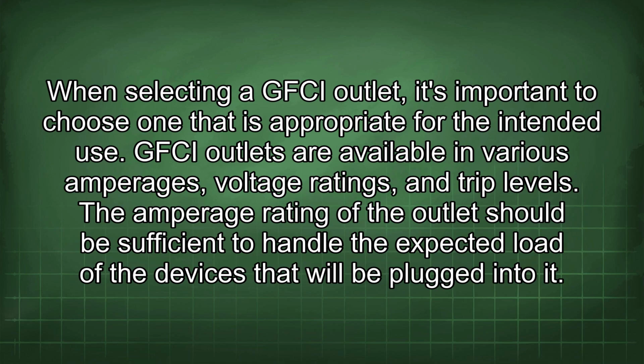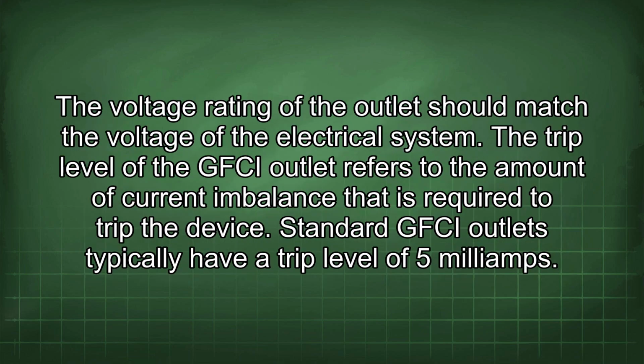When selecting a GFCI outlet, it's important to choose one that is appropriate for the intended use. GFCI outlets are available in various amperages, voltage ratings, and trip levels. The amperage rating of the outlet should be sufficient to handle the expected load of the devices that will be plugged into it. The voltage rating of the outlet should match the voltage of the electrical system. The trip level of the GFCI outlet refers to the amount of current imbalance that is required to trip the device. Standard GFCI outlets typically have a trip level of 5 mA.